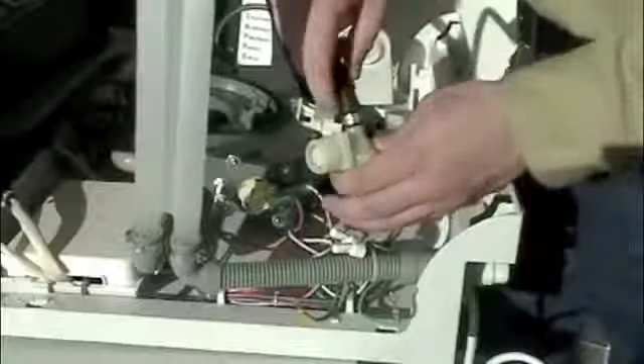The next thing that we want to look at is on the inside of our unit here. And as you can see, I've taken this apart so that you can see it easier. This is our electronic inlet valve. It has two wires, a solenoid assembly, the filter, and the inlet assembly itself. And then on the other side we have the outlet, which goes over to our flow meter. I'll show you that in a minute. A lot of times we'll find that the unit fills up really slow, and we end up having an E1 error code on the display at the front of the unit.